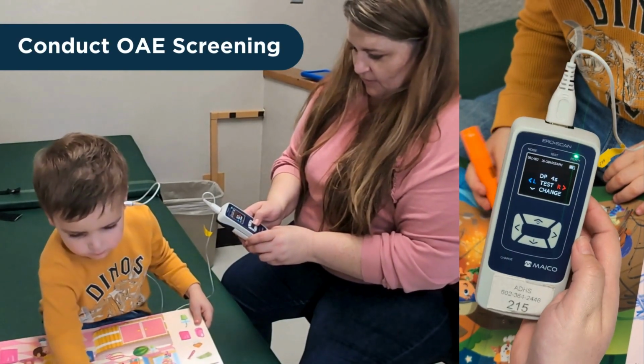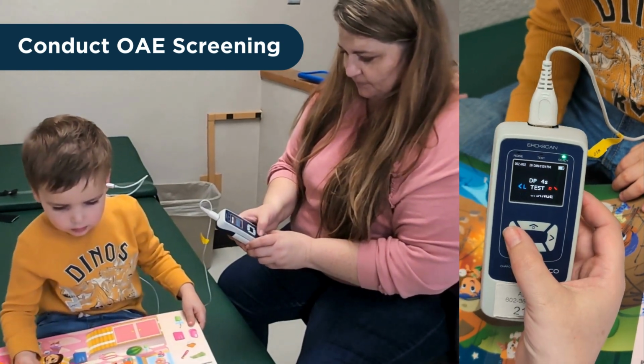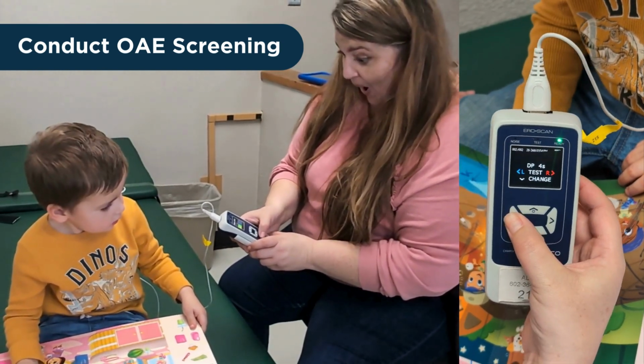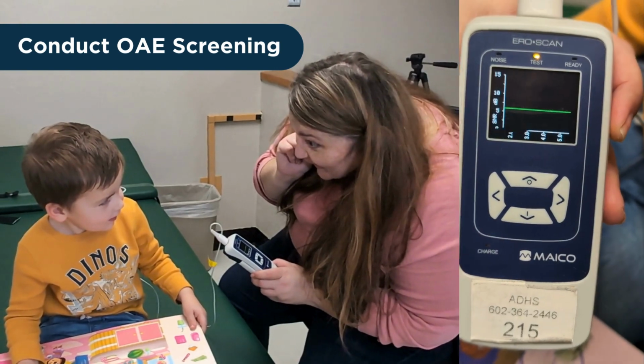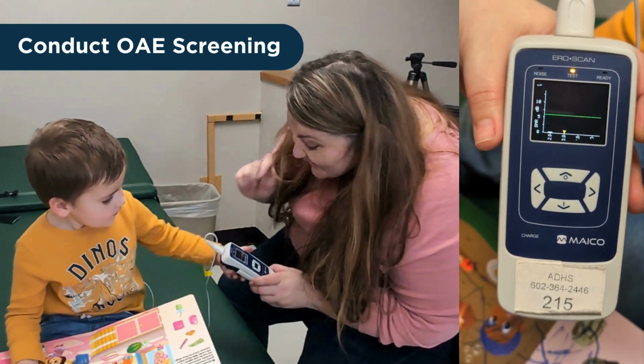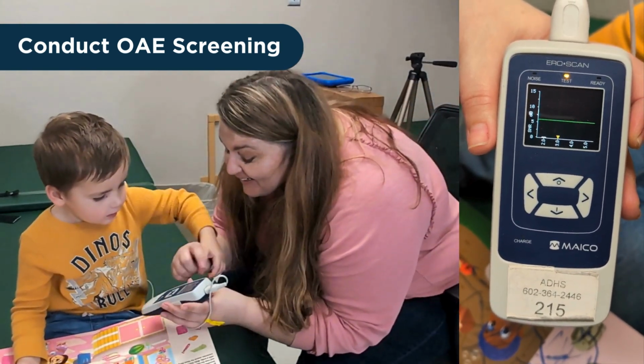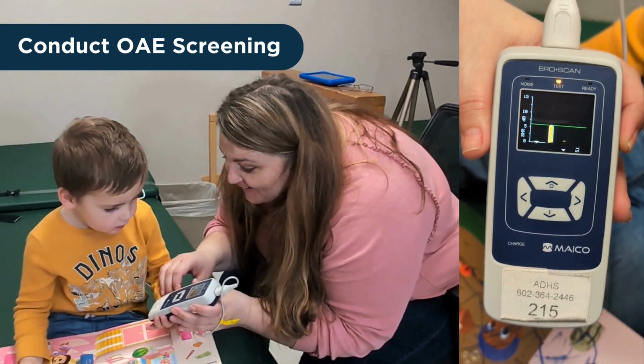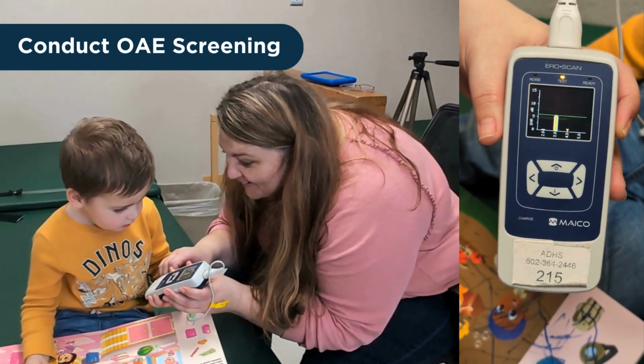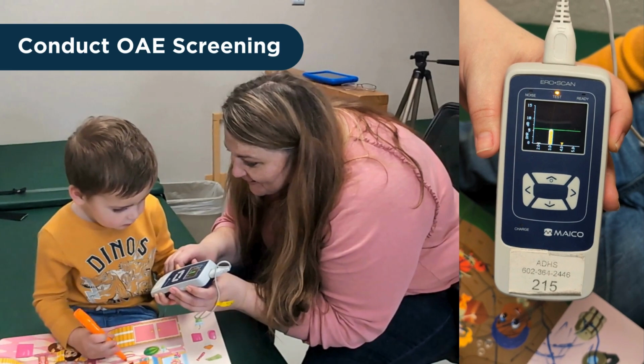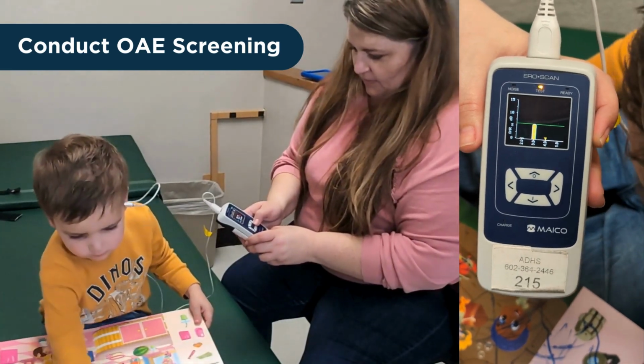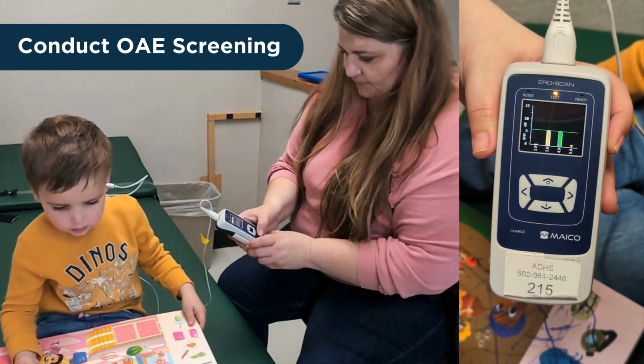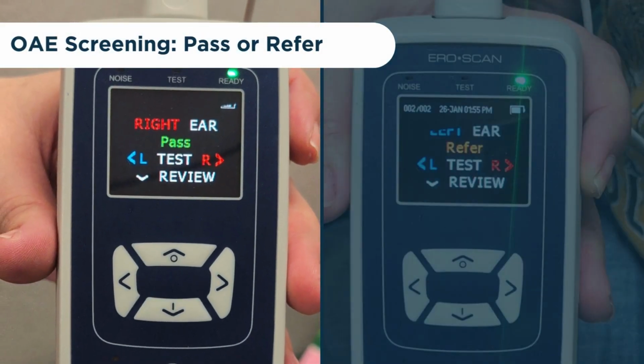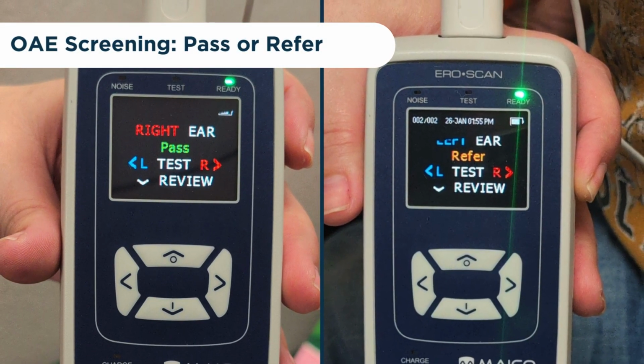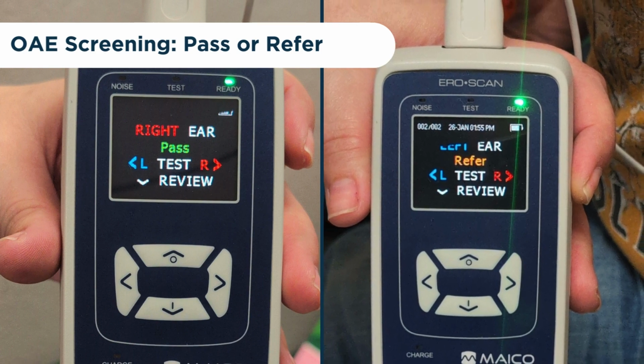Next, turn on the equipment. Press either the left or right control panel button from the test menu to select which ear is tested. The probe check and screening should begin automatically. Some equipment will indicate the progress of the test, showing sound frequencies or pitches, while others will simply indicate that the test is in progress. The display on the device may give you an error message if there's not a good probe fit or if too much noise is detected. After the test is complete, the screen should display pass or refer. Record the result and remove the probe from the ear.